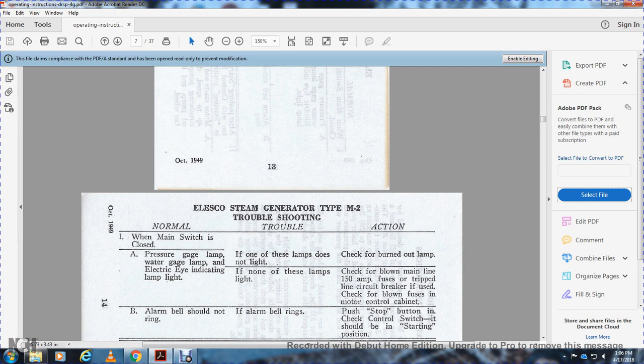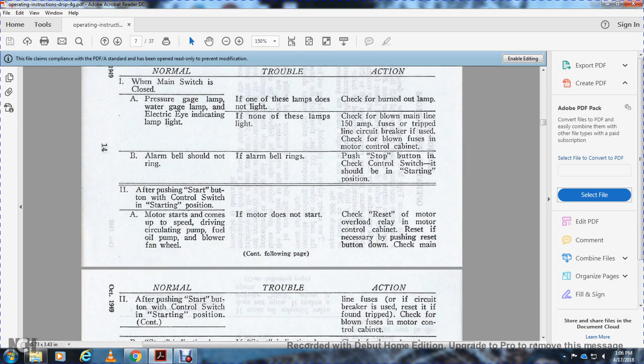Alright, normal. B, the alarm bell should not ring. Trouble: if the alarm bell rings, push the stop button and check that the control switch is in the starting position. Two, after pushing the start button with the control switch in the starting position, A, the motor starts and comes up to speed, driving the circulating pump, the fuel oil pump, the blower, and the fan wheel. If the motor does not start, check the reset of the motor overload relay in the motor control cabinet. Reset if necessary by pushing the reset button down. Check the mainline fuses and the circuit breaker. If they are fine, check for blown fuses in the motor control cabinet.